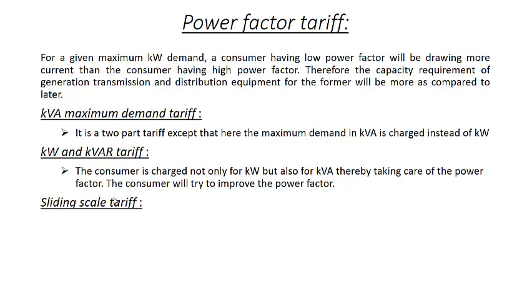In this case, the consumer will try to improve the power factor, and when it does, the kVAR requirement by this consumer, or the kVAR that is supplied by the utility, will be less, and hence the charges for the consumer will be reduced when you improve the power factor.